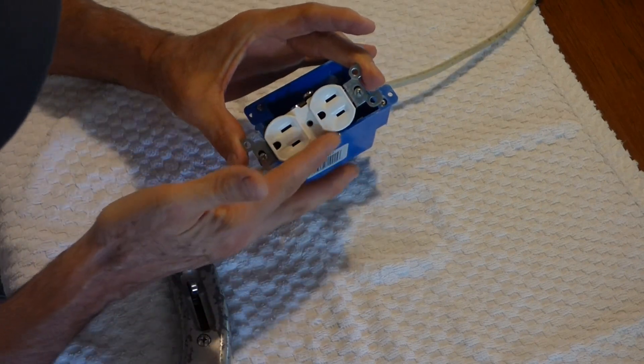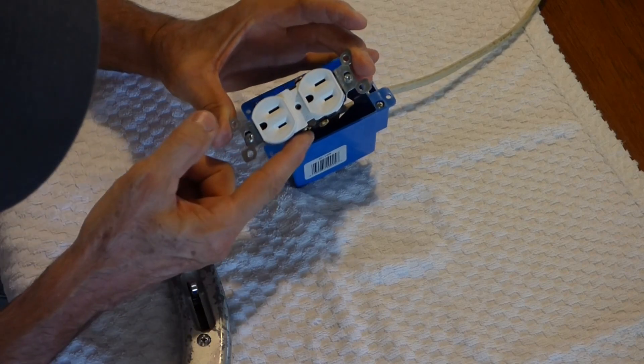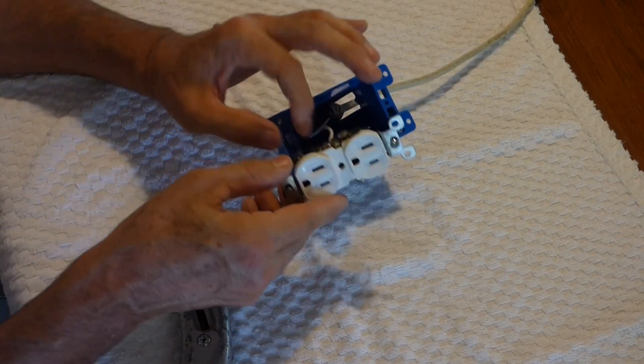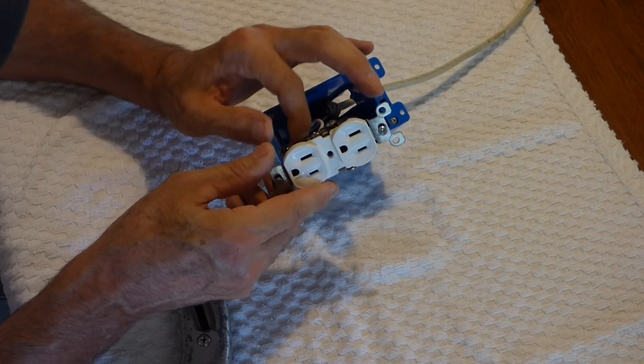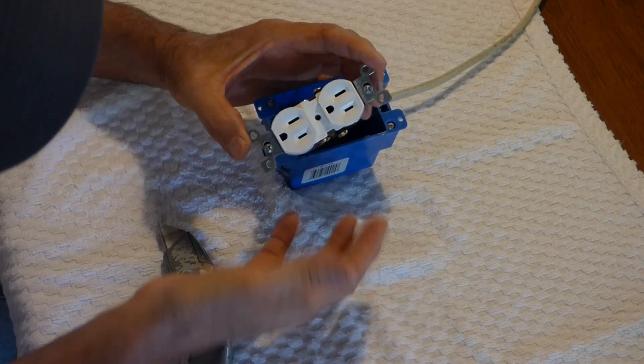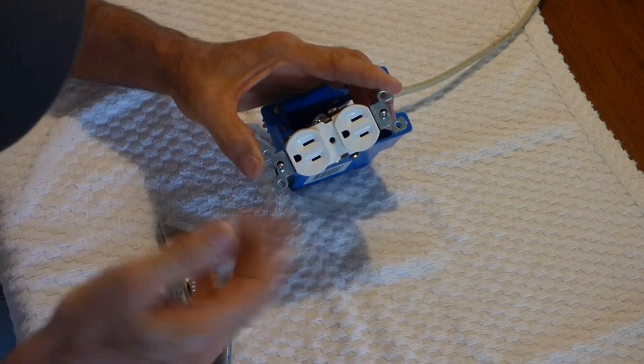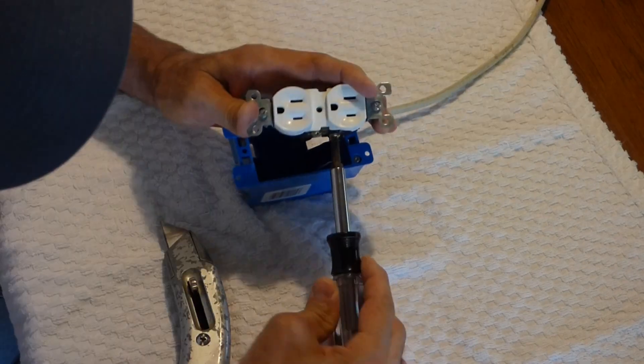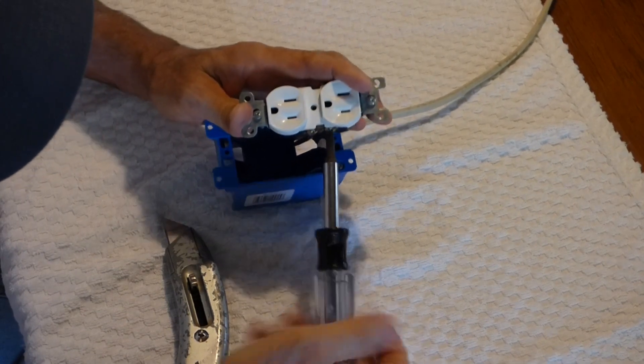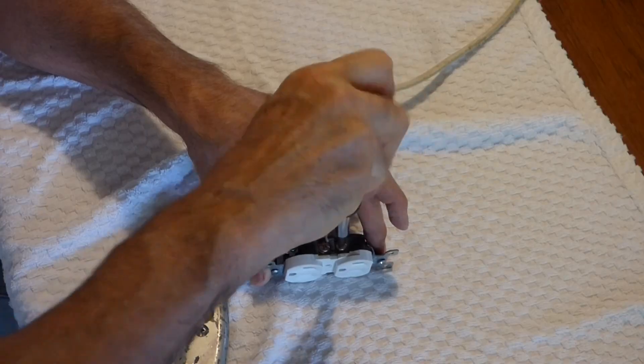The other thing that you want to do is tighten these screws that you're not using down. When they're left like that, they're sticking out. These are tucked in nice. And when those are sticking out, you've got the same problem where they could be shorted out by the ground wire, another wire, if you've got other wires in the box. So it's very important, tighten these down, get them out of the way. That'll save you from problems.